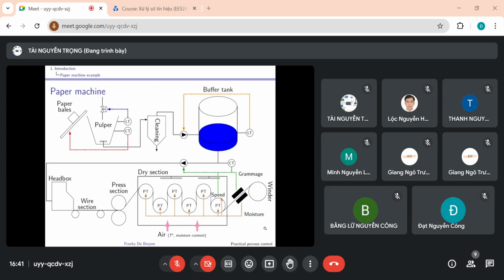Let us have a look at the level control that you see here in blue. The level of the pulper is adjusted using the control valve, which itself is used to adapt the water flow inside the pulper. Here it is very important to meet the level set point as closely as possible. The process from control valve to level is an integrating process, and we'll see that a PI controller needs to be used here. This is covered in section 6 about level control.